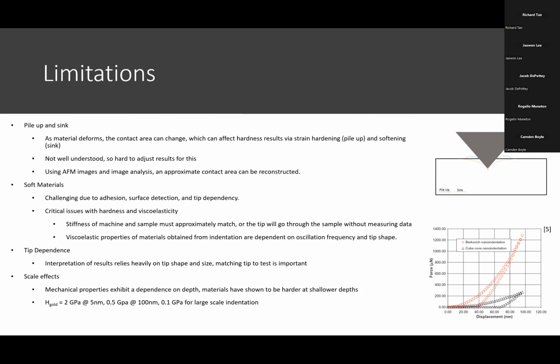Another limitation is using it on soft materials. So soft materials are intrinsically challenging because they have adhesion, surface detection is difficult, and there's a high dependency on the tip. But there's also critical issues with measuring the hardness and viscoelasticity. So with hardness, you want your sample and tip to approximately match in stiffness, or else the tip will go through the sample without measuring any data, and that's never good. You want your data. The second would be the viscoelastic properties of the material obtained from nano indentation are very dependent on the oscillation frequency that you use and the tip shape, so you have to account for that.